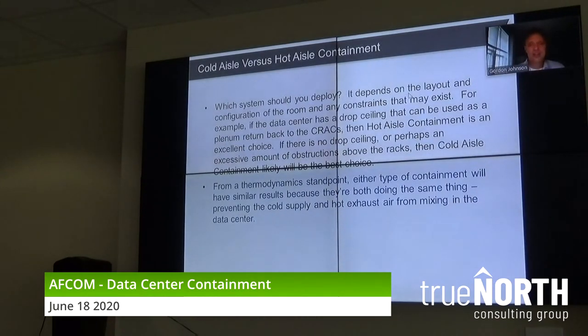Like we said, with hot aisle containment, you're walking into a cold data center. The customer would say, you know, it's 75 or 72 when I walk in, I can go a tiny bit higher compared to the cold aisle containment. Maybe it's 90 when he walks in. He goes, I don't want to go any higher, even though the server equipment's getting the exact same temperature. But again, just remember, from a thermodynamic standpoint, either type has similar results.